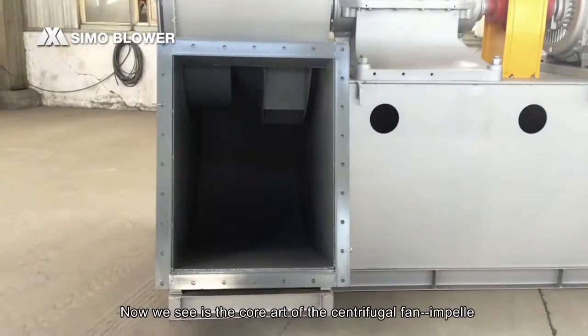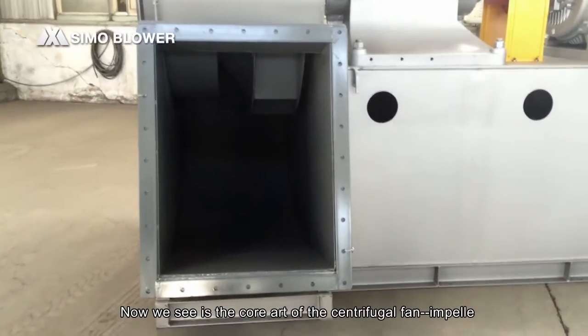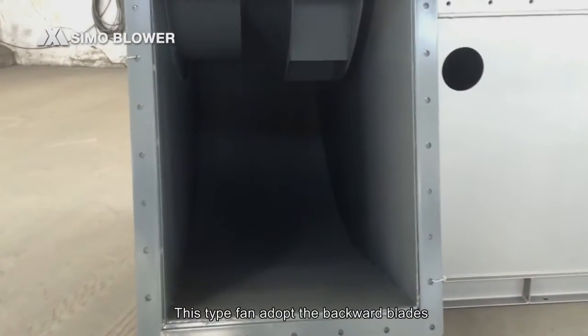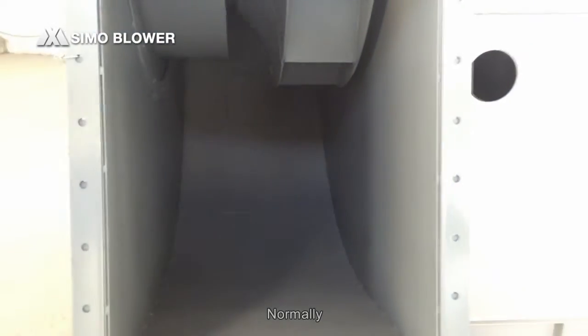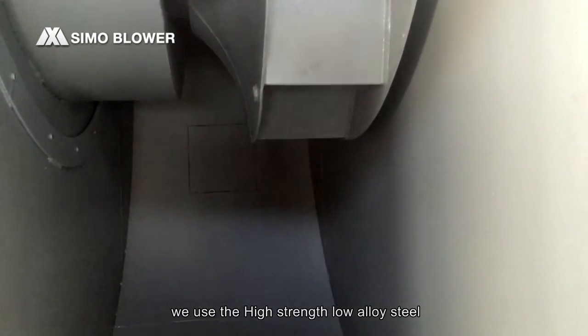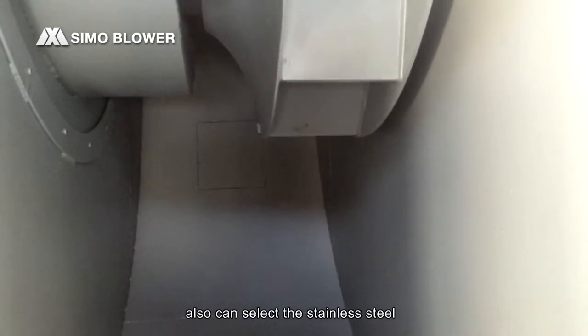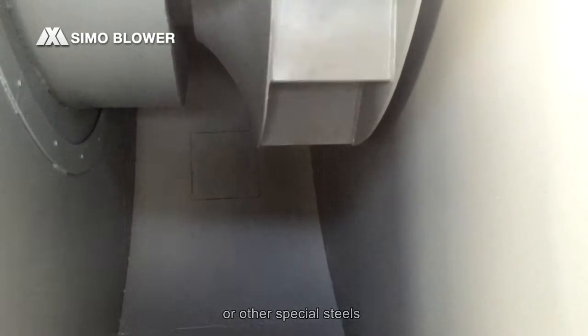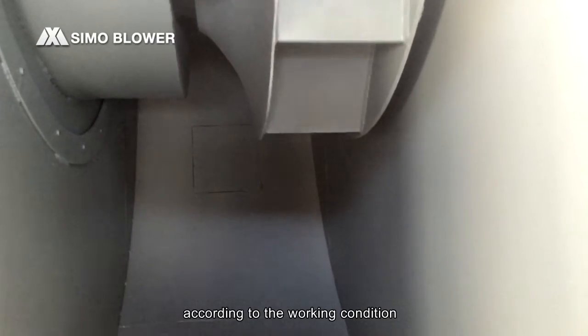Now what we are seeing is the core part of the centrifugal fan — the impeller. This type of fan adopts backward blades. Normally, we use high-strength low alloy steel, but stainless steel or other special steels can also be selected according to the working condition.